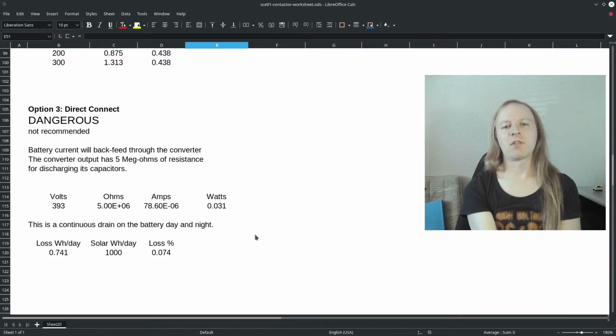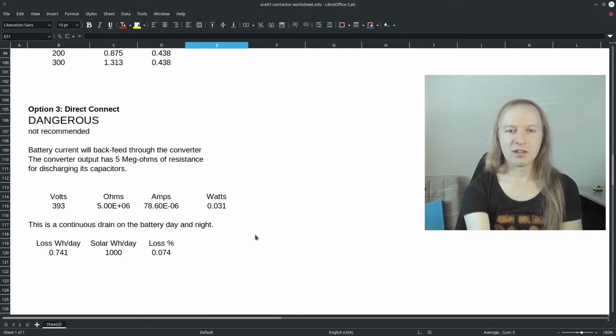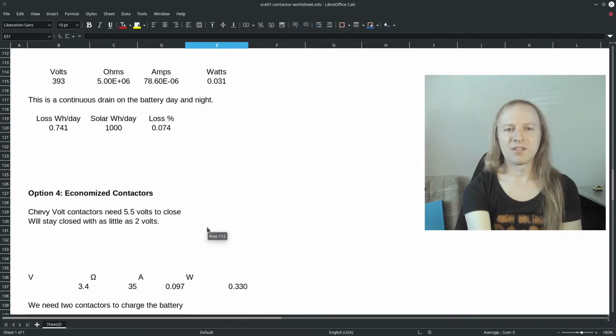Keeping with the theme of worst case scenario, we'll assume a low value of 1 kilowatt-hour from the solar array. We find that's 0.074% of the energy lost here, a lot less than the 0.5% from the diodes. But we still don't recommend this, and 0.5% is still not that big of a deal.